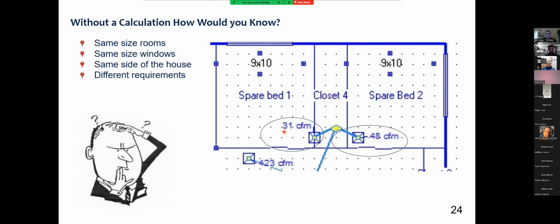And then I ask my customer, as I'm showing them this on our virtual assessment, can you guess why this room might need 50% more air than this room? And probably about 15% of the customers we talk to come up with it right away. You have two outside walls, but most of them say, I don't know, the window's larger or which direction it's facing. But just keep in mind, rooms that are on the corners need more air. Rooms that only have one outside wall need less air. That will help you even if you're not doing a load calculation.